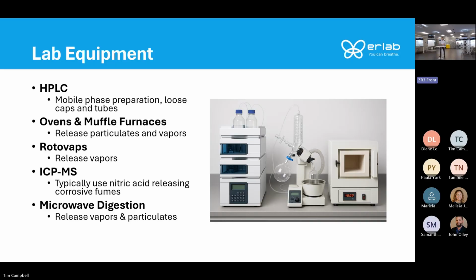and any other equipment such as microwave digestion, where you're using acids to dissolve different samples. It's going to be heated. Sometimes those are just on the bench. They're releasing into the space. Same with the ICP-MS. That typically releases nitric acid. If you have an ICP-MS, you may see some of the metal grates corroding. That means you have corrosive fumes in the lab space. So that's something you want to think of.